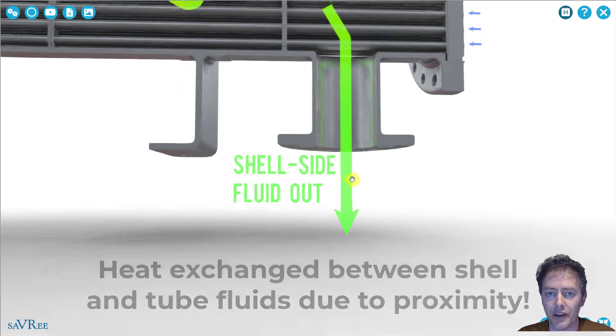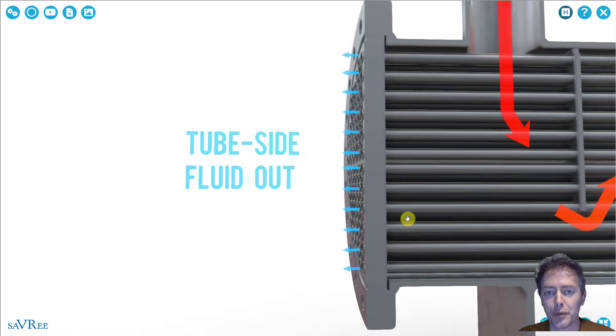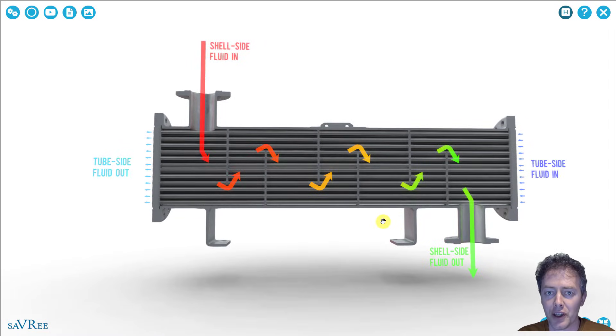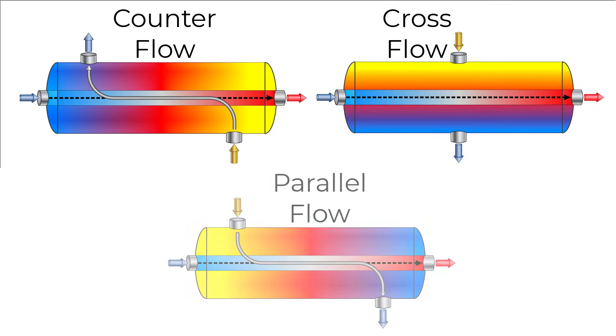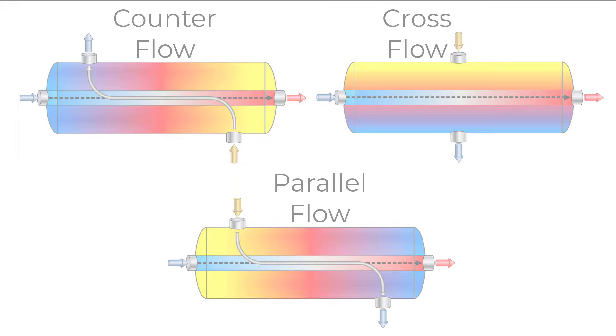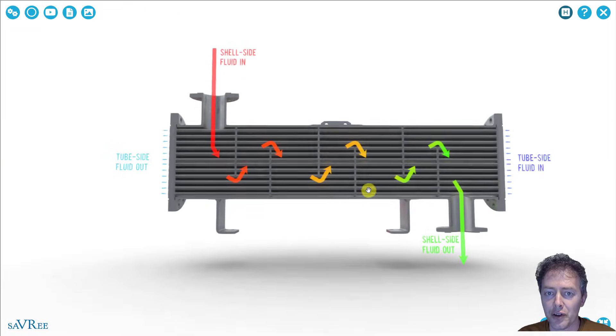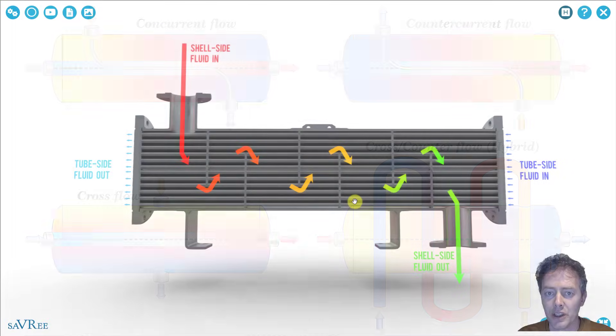On the other side, we've got a cold fluid going in and as it passes through the heat exchanger it gets slightly warmer, going from dark blue to light blue. The two fluids are flowing in counter directions — the shell side fluid is flowing to the right and the tube side fluid to the left. You have three main types of flow through all heat exchangers: counter, cross, and parallel. In this heat exchanger we're using not only counter flow but also cross flow, as the shell side fluid is directed across the tubes several times.